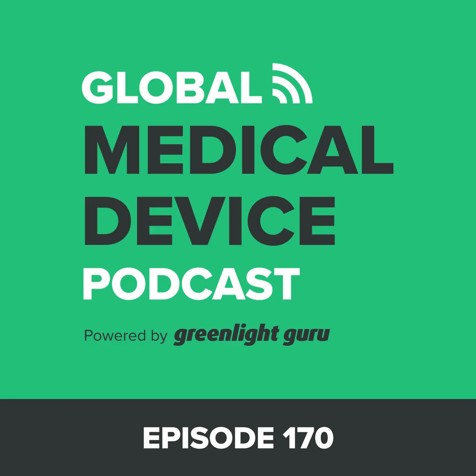Absolutely. I think a pre-sub is vital to almost any submission to the FDA. It's a chance to get formal feedback from FDA. They have to put down in writing what their stance is on a particular issue. And that allows you to move forward with some confidence that your testing plan will actually meet the FDA requirements. You don't have to guess on this. You don't have to spend a whole bunch of money designing a testing plan or even a clinical study plan without that FDA feedback, and formal feedback, so that you have it in writing. You can refer back to it and say, we followed this plan, and this FDA review team agreed that it would be sufficient to meet the intended use that we describe.